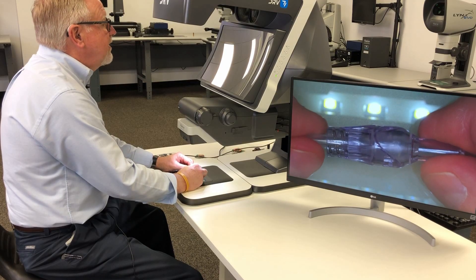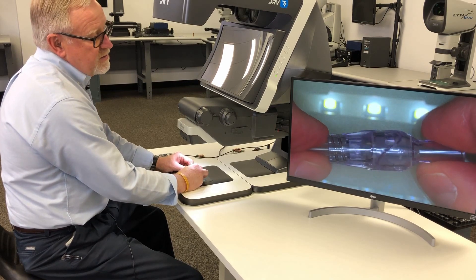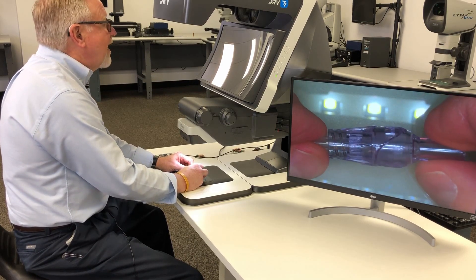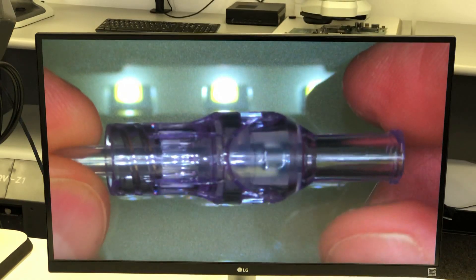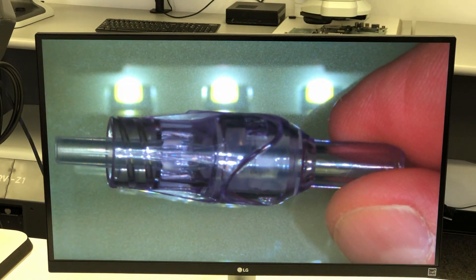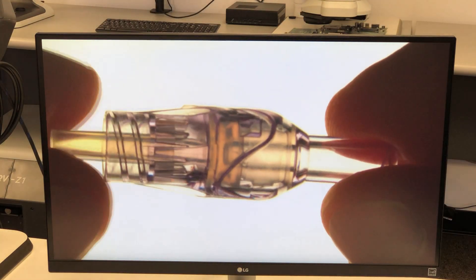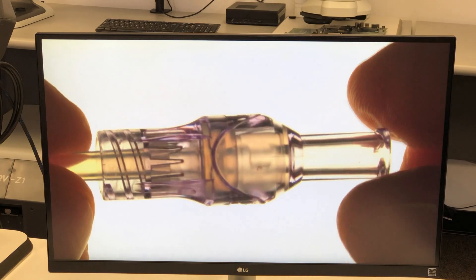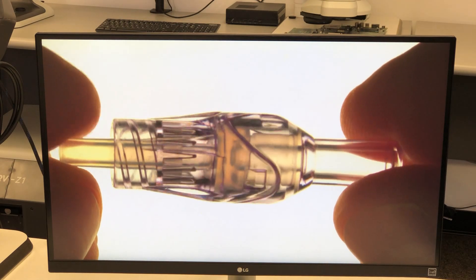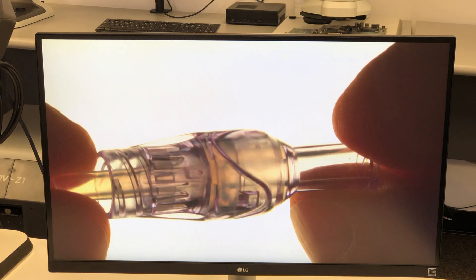The DRV has fully adjustable LED surface illumination. Some parts require through lighting or transmitted lighting, so the DRV also offers the option of an LED sub-stage light. We can turn off the top light and bring up backlighting so we can light through the part and look for flow lines or other molding defects.